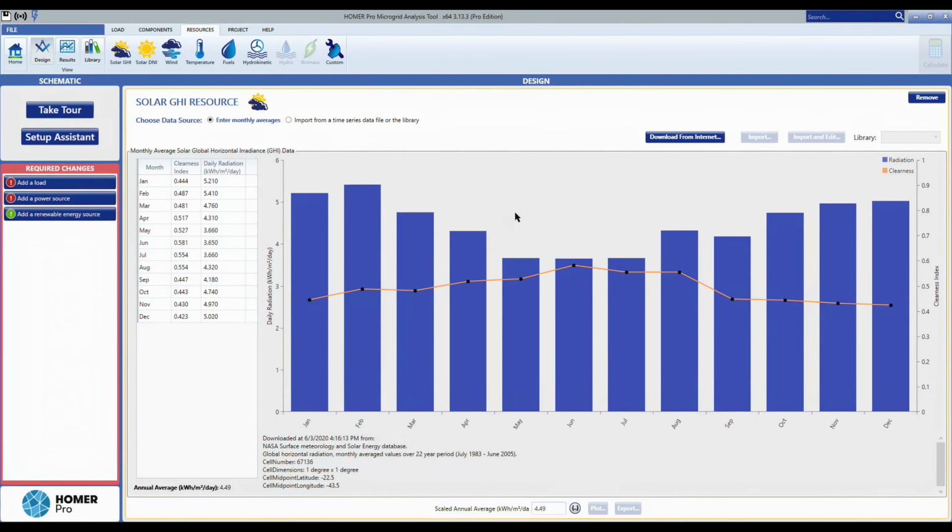So the question says the worst months of the year have 4 kilowatt hours per square meter per day, but here we can see 3.66, 3.65 and 3.66. So the minimum number in the worst months of the year, which are May, June and July since they are in the southern hemisphere, is 3.65 kilowatt hours per square meter per day. It's close enough to what we have in the exercise, but let's continue with this new number.